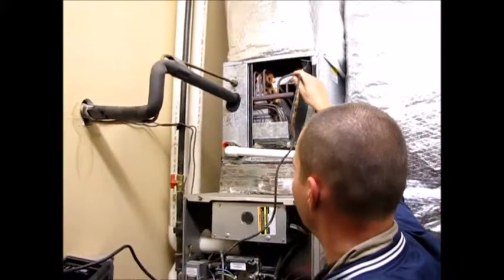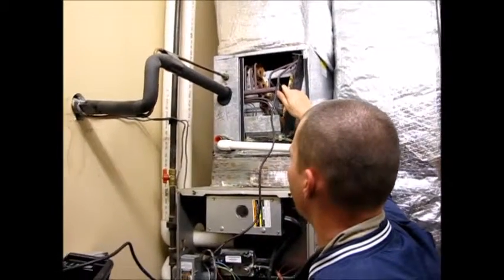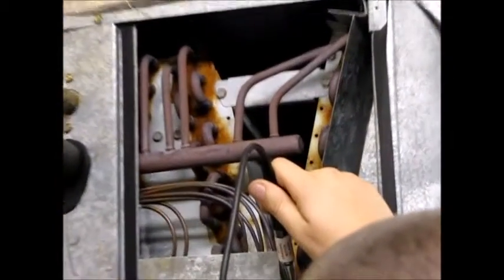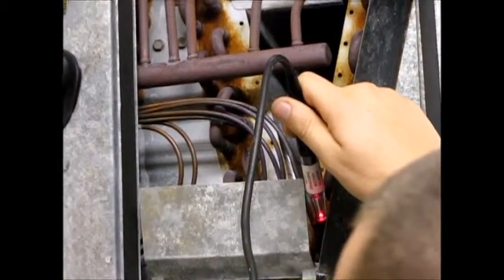Just to show you again, to make sure that we can double-check what area of the coil we're losing refrigerant at. The closer I get to the bottom of these U-bends here, it seems to be where our culprit is leaking from.